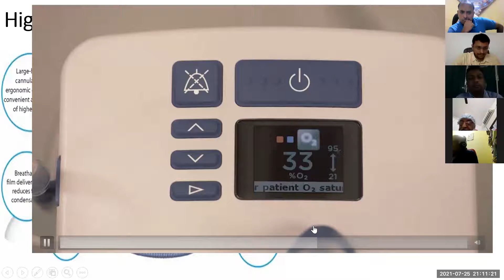So here what happens, one thing I'd like to tell you is this: the oxygen flow, the flow rate you can set for the gas flow, and then the amount of oxygen you give through that meter, that will determine the FiO2. You will get the reading of FiO2, but you cannot, like on a ventilator, have a switch to directly set the FiO2 to 30-40%.